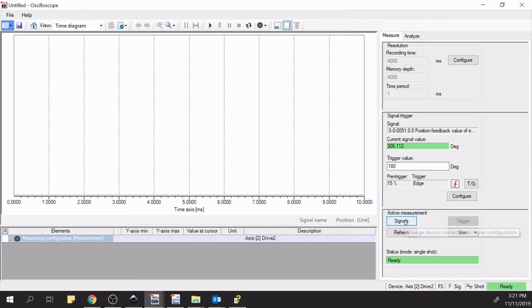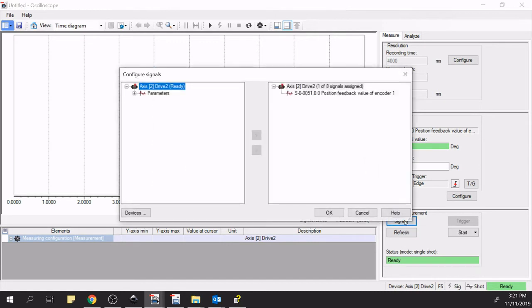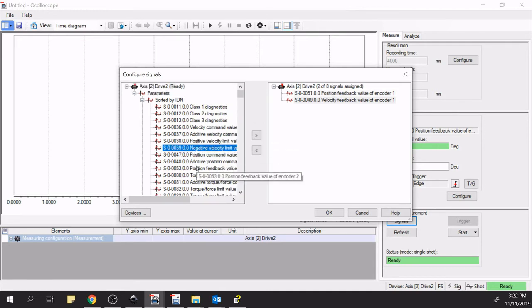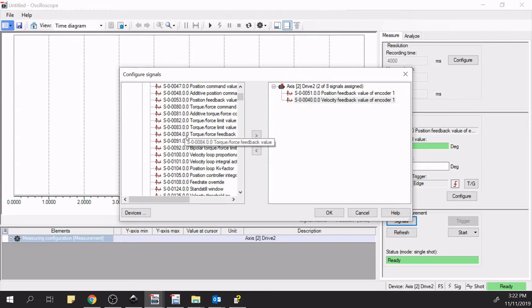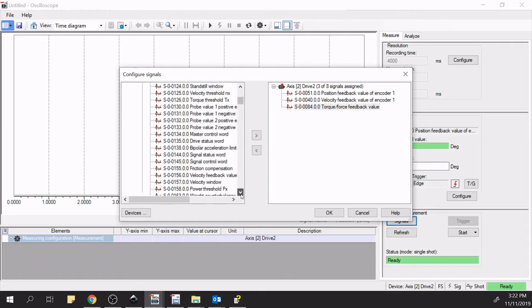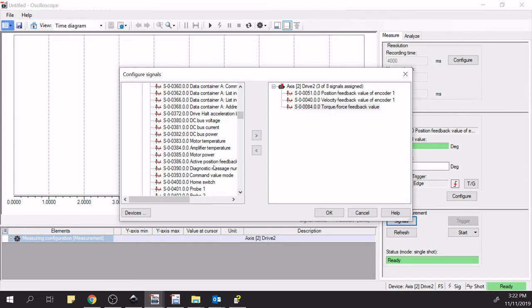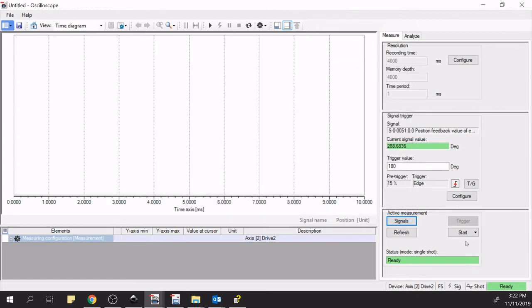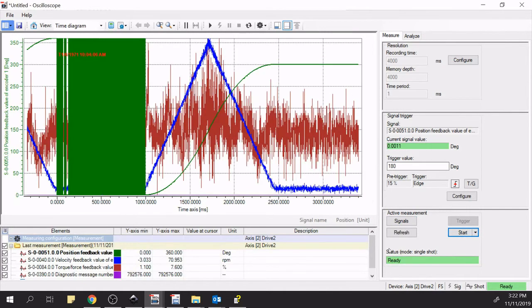Now we need to select signals to record. The position feedback is already listed. Let's add a few more — velocity feedback and torque feedback, which is S-0-0084. We could also add diagnostic message, which makes sense. Clicking OK and starting the recording — as you can see, the axis has crossed 180, the trigger fired, it's recorded, and here it is. Now we have a recording and can move to the Analyze step.